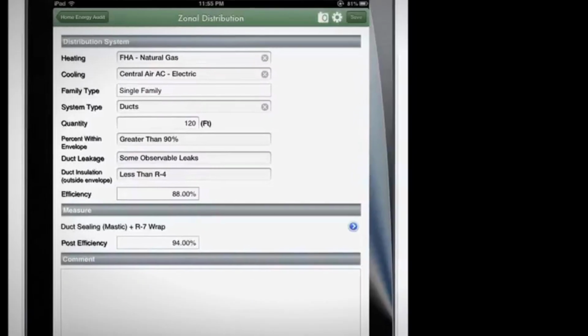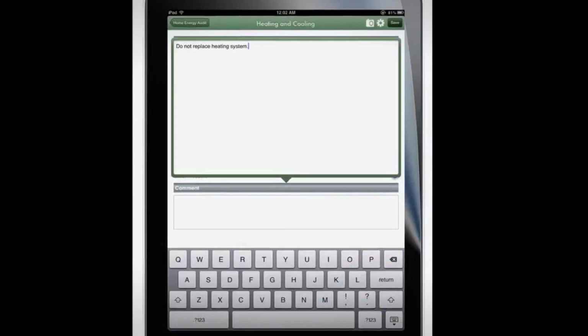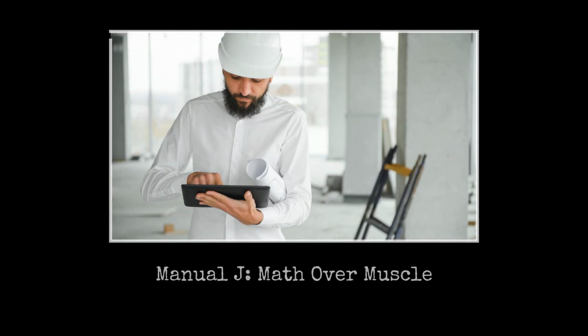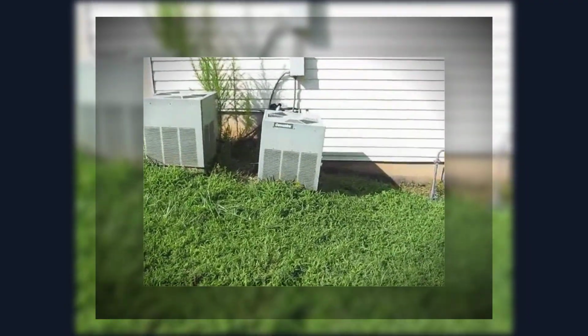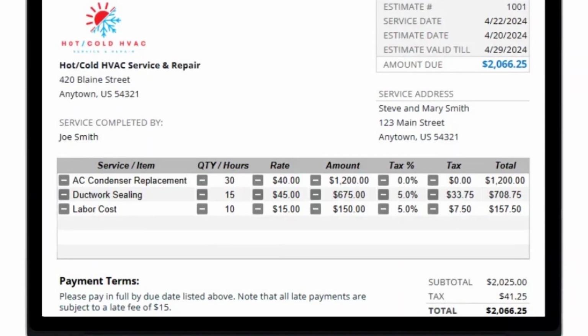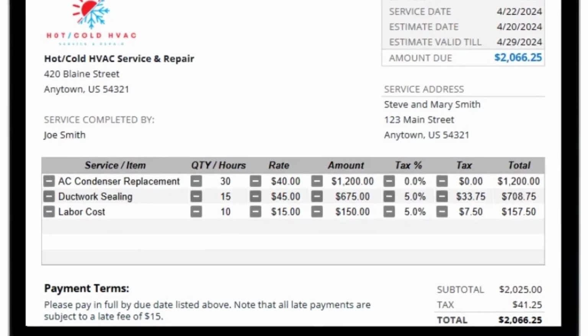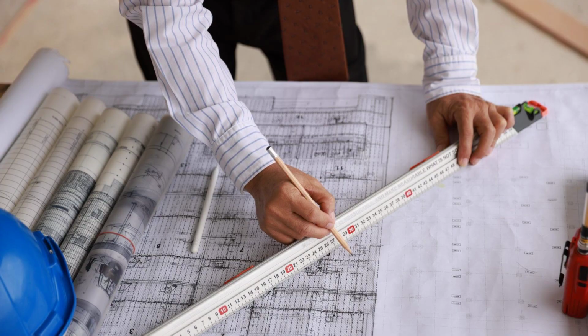How do you know if you're being oversold? One way. A Manual J calculation. It accounts for square footage, insulation, windows, orientation, climate zone, and air infiltration. If your contractor is sizing by eyeball or matching whatever was there before, they're guessing with your money. Ask for the Manual J.